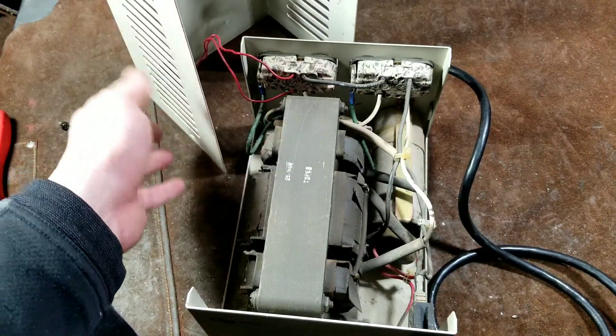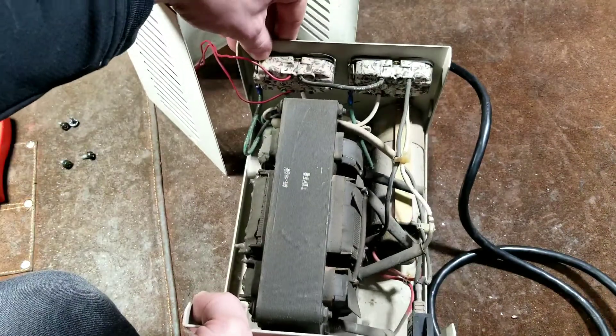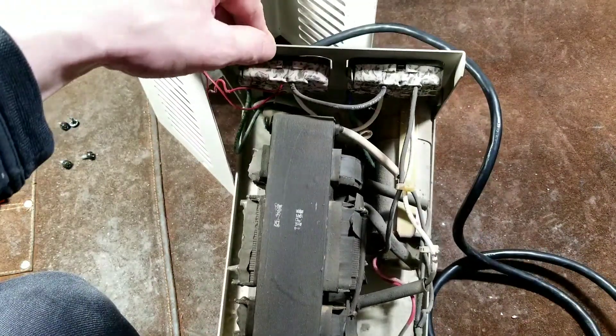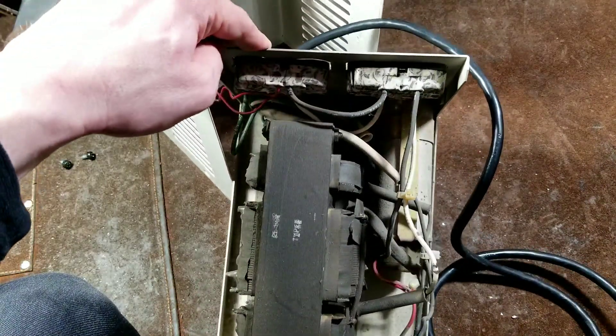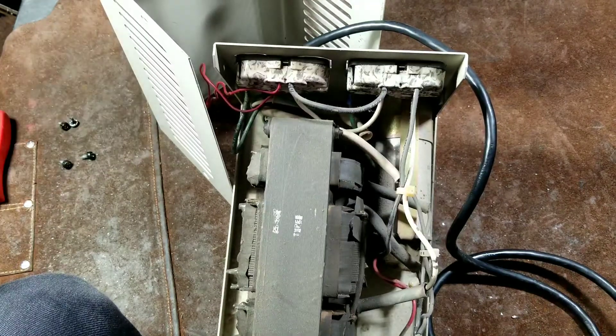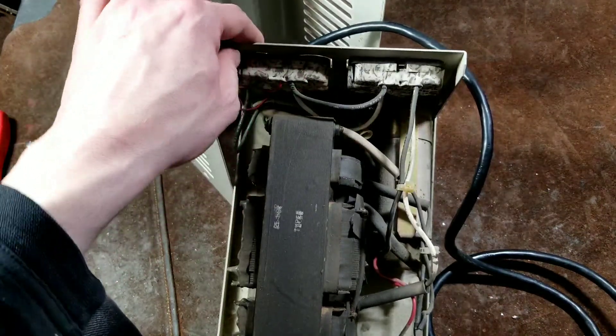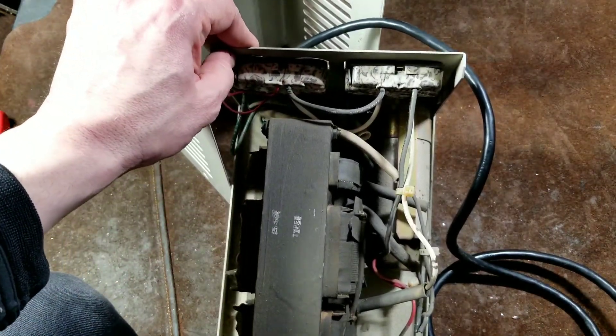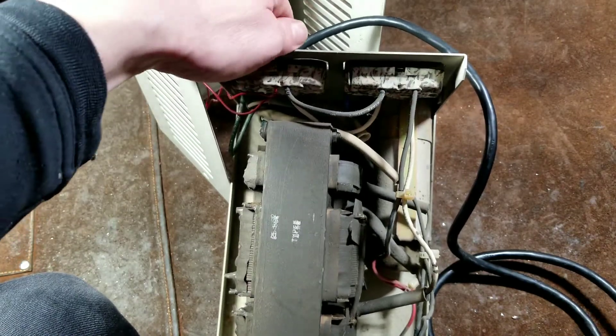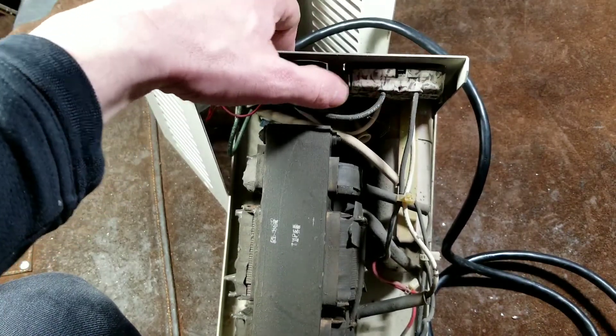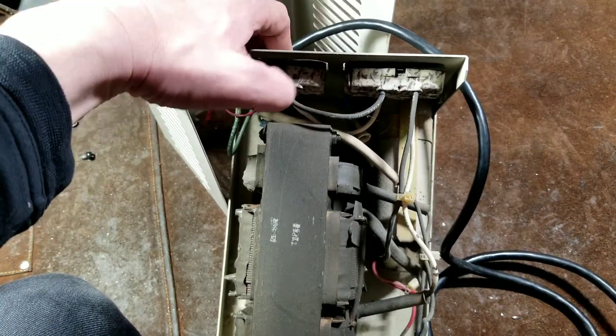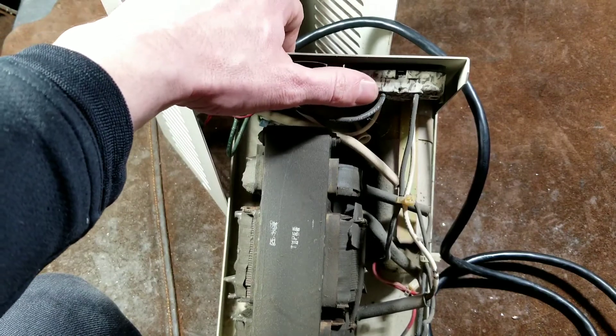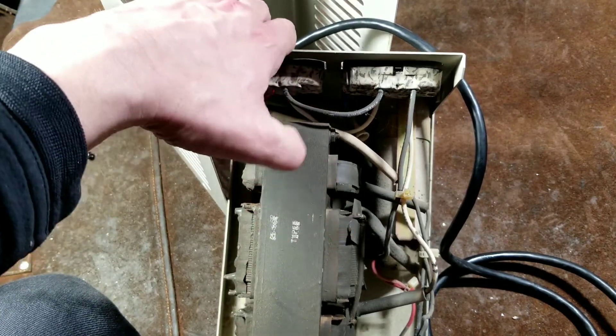So we can see inside here that these really aren't super intended for the greatest amount of noise filtering. An isolation transformer will do much better. These are set up really for that voltage regulation. We don't have any capacitors, we don't have any form of surge protection. These are relying a lot on the design of this transformer.